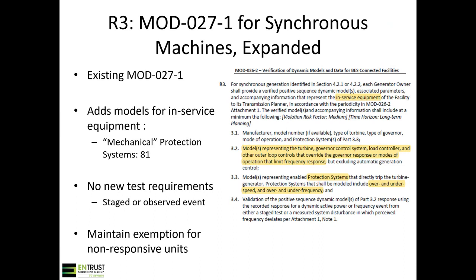R3 of Mod 26-2 is the comparable version to Mod 27-1 for synchronous machines. Again, added detail, expanded a bit, but there's really less in governor systems that require capturing. So we added what we termed mechanical protection systems, correlating more with the mechanical side control. That's 81, being over and under frequency elements. Again, no new test requirements. The functional requirements for turbine governors and testing is very similar to what we had before.